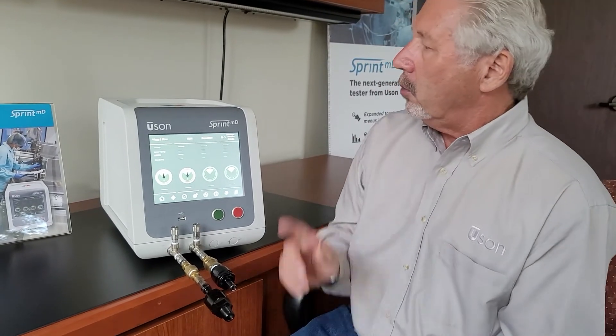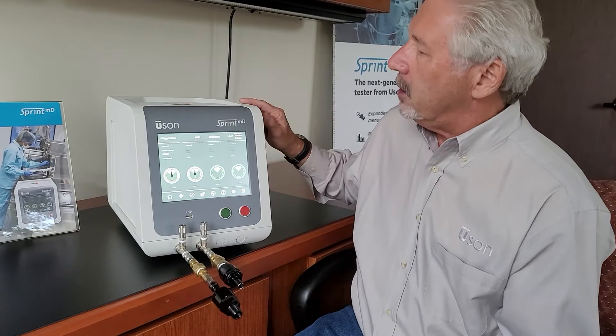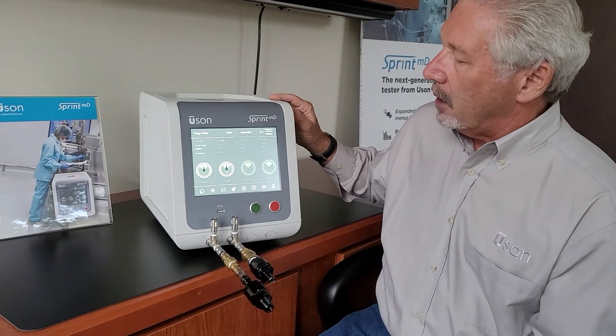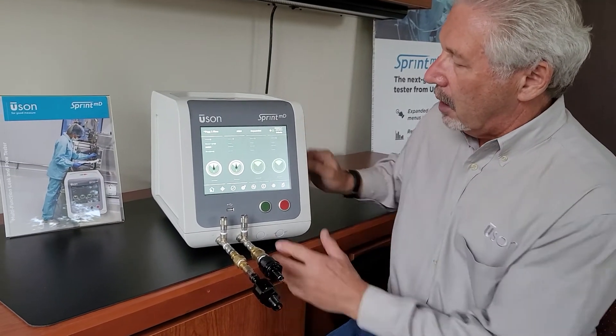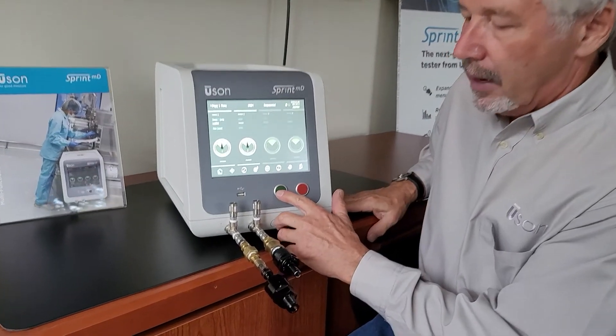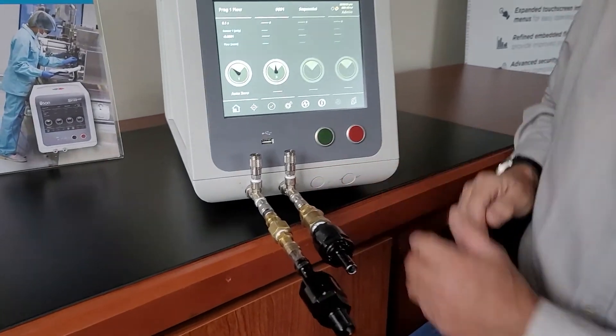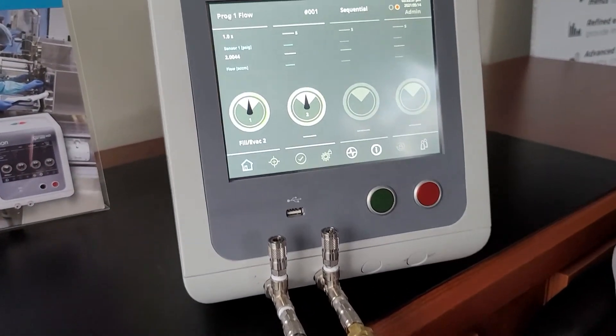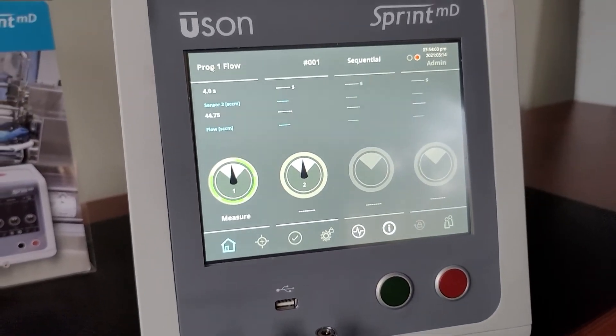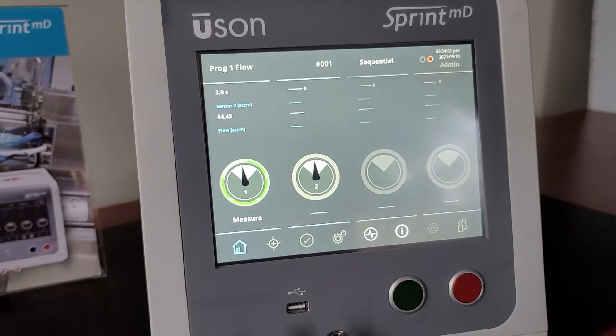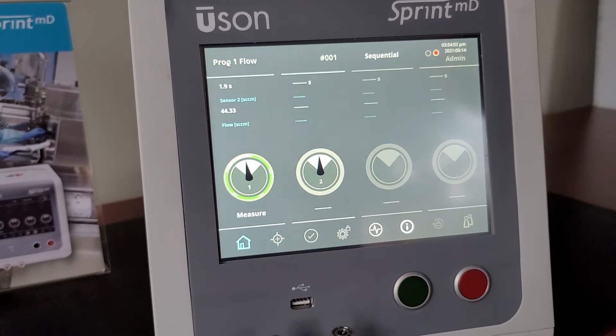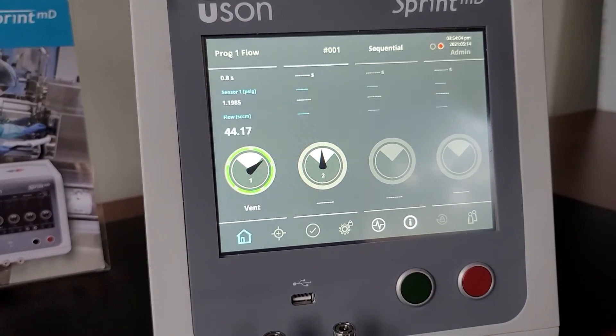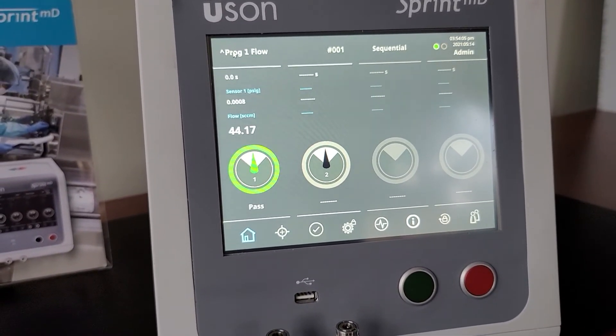With the Sprint MD tester and a mass flow configuration on channel one, I'm going to run a mass flow test on the part at 2 psi. When the part is operating correctly, it should flow between 40 and 50 cc per minute — which it does.